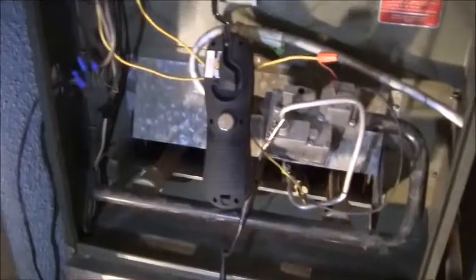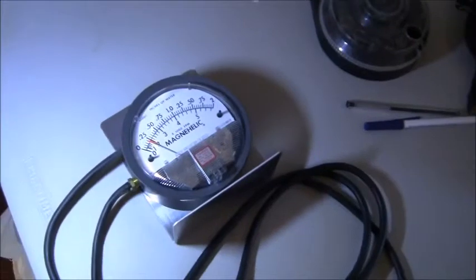Okay, now I want to get some airflow readings to determine what's going on with that. In an effort to do that, we're going to utilize this Magnehelic gauge. Okay, so let's go ahead and bring the Magnehelic gauge over. Now I want the unit to be on in heating. When you use the Magnehelic gauge, this needs to be flat. So I want to make sure that that's as flat as possible.